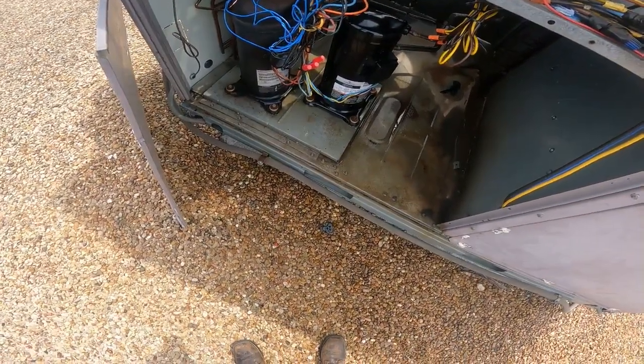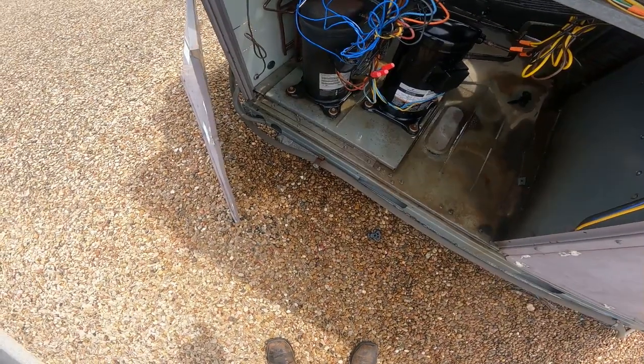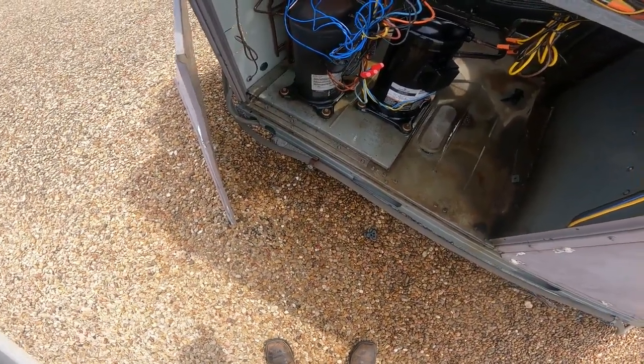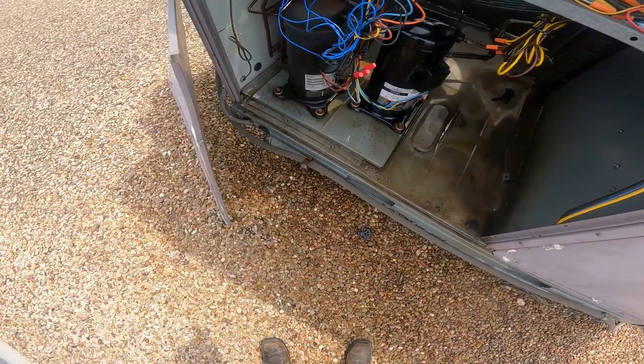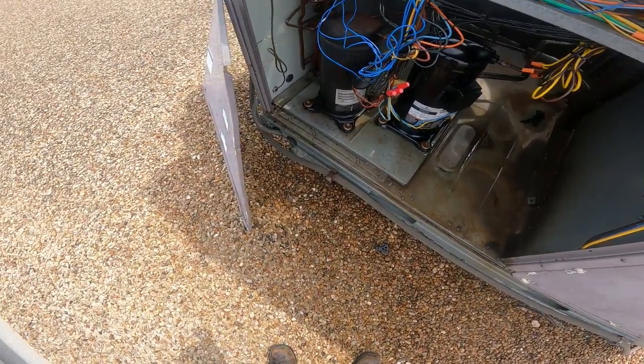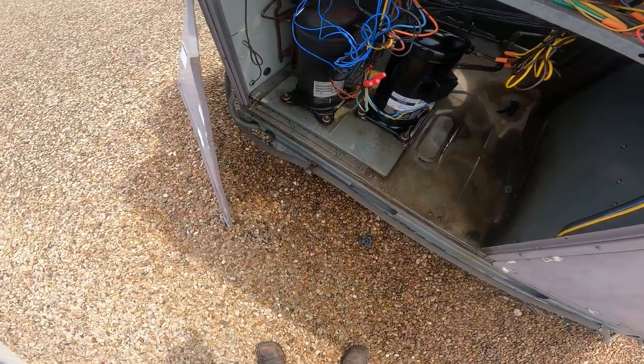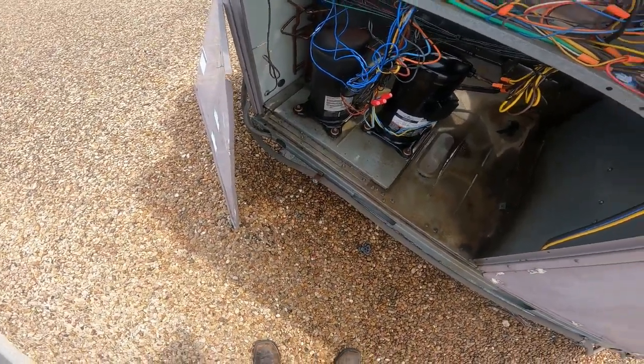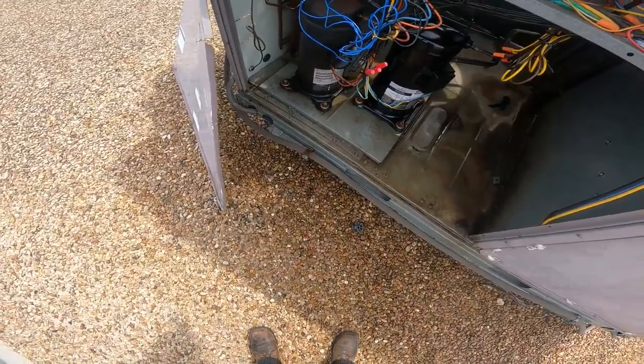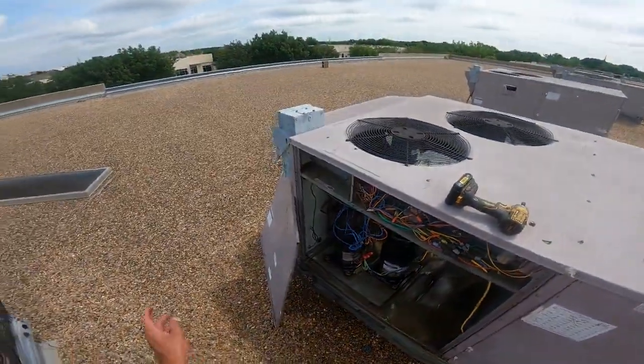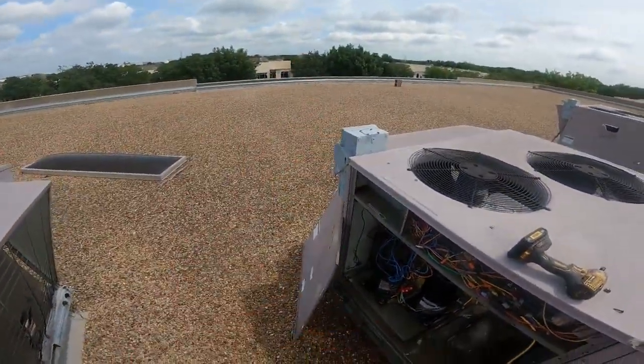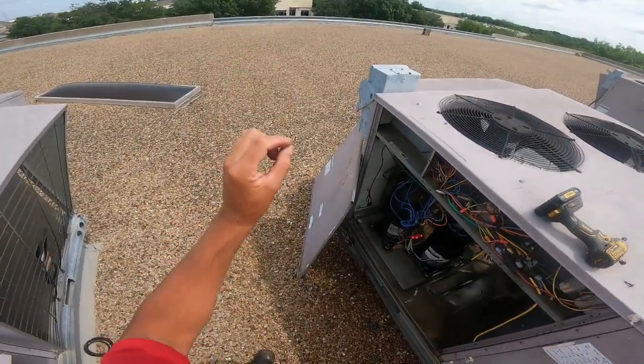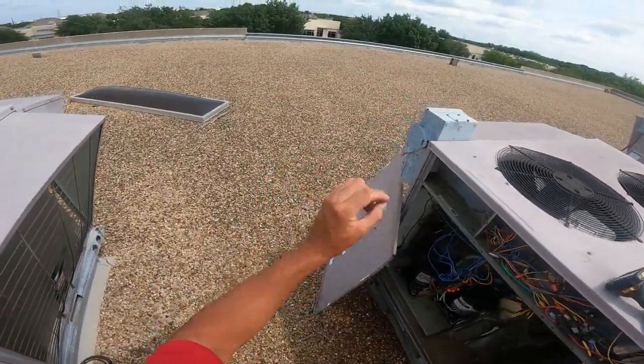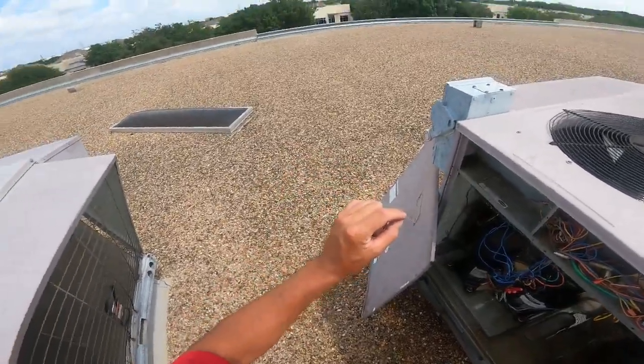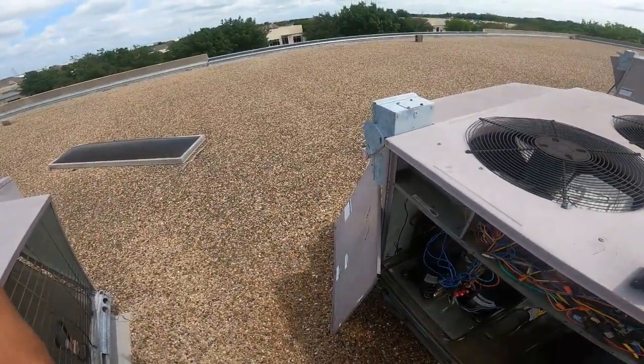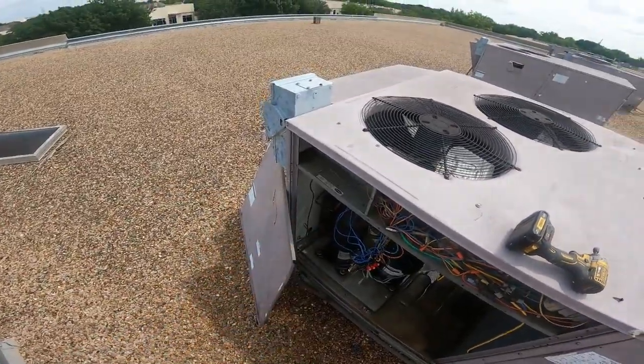I cannot believe it, people. Stop bypassing safeties, they are there for a reason. And if it doesn't work, then replace it. It's that simple, it is literally that simple. I have all these pressure switches in my truck, always keep them with me. So guess why? Because I don't have to bypass them. Now let's say I don't have one. I may bypass it after I make sure it's working fine, but I'm only going to bypass it long enough for me to run down to the parts store, get one, and come back and put it in.